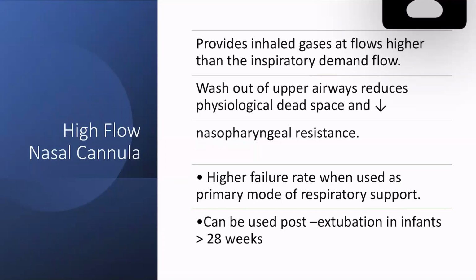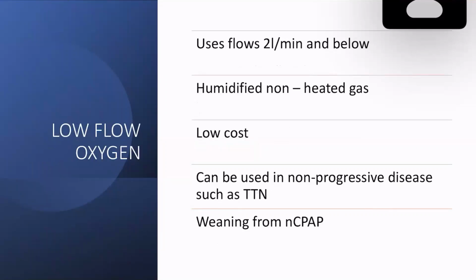So basically, the devices that give high flow nasal cannula usually have a humidifier, and then the machine itself, maybe like a Vapotherm, and then you use the nasal prongs to deliver the high flow. And then low flow oxygen is what is most commonly used in low resource settings. So you'll be using flows which are 2 liters per minute and below. The gas is humidified, but it's non-heated.